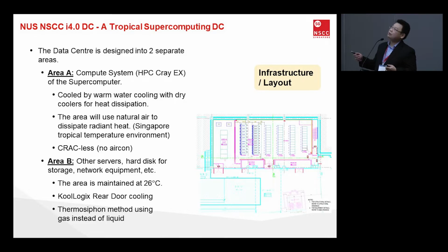So the whole area B is using the KoolLogix systems, as mentioned. Okay, thermal siphoning. Area B is based on gas base. Okay, there's no water within that particular area. All right, and the area temperature is maintained at 26 degrees. So this effectively tells you that we actually don't need any CRAC units within the area. So hence, there is no CRAC unit in the area. All right, later on when we talk more about area B, I'll go into more details.